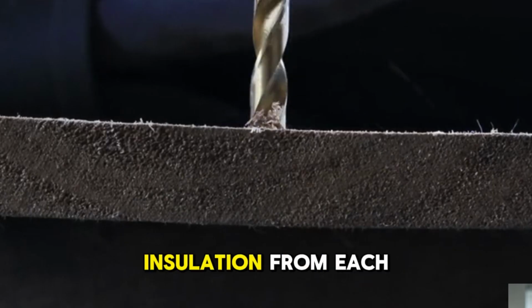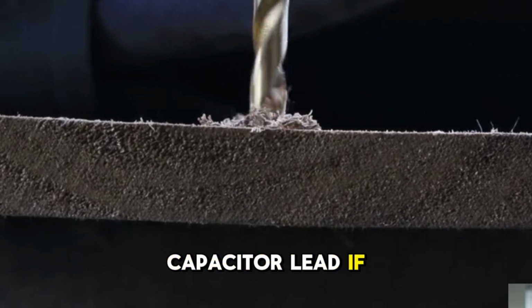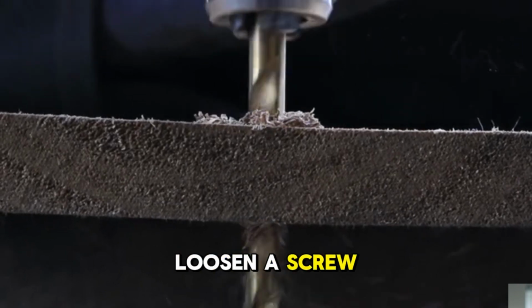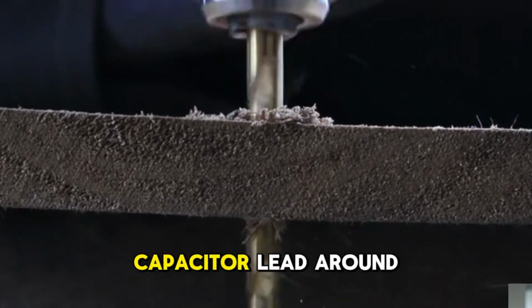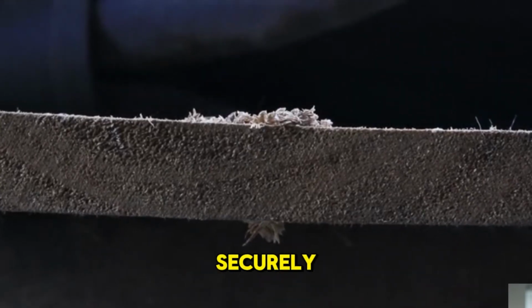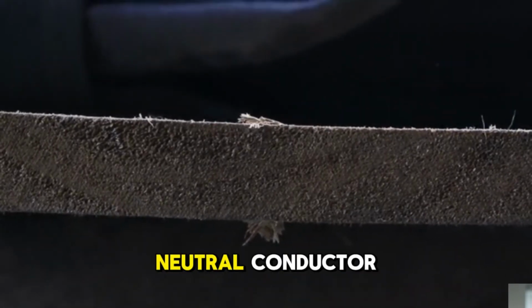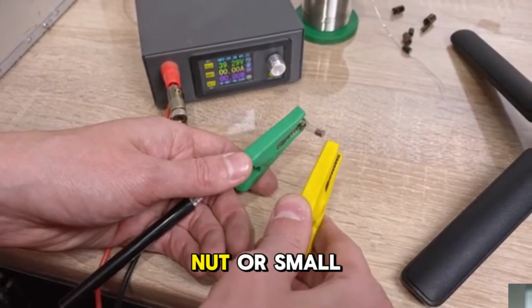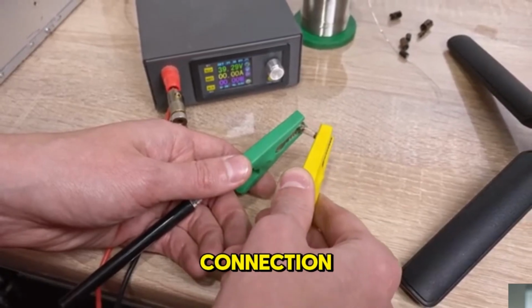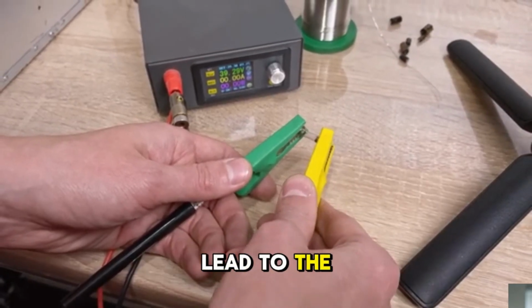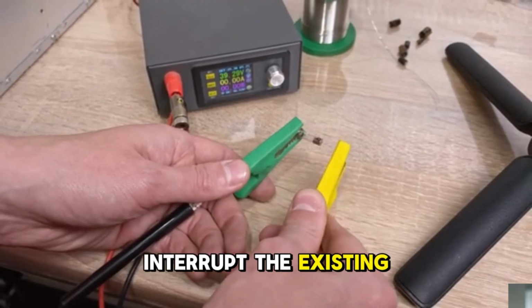Strip about 1/2 inch of insulation from each capacitor lead, if they're insulated. Loosen a screw on the ground bus bar and wrap one capacitor lead around the screw, then tighten it securely. The other lead connects to the main neutral conductor. You may need to use a wire nut or small crimp connector to make this connection, attaching the capacitor lead to the neutral line in a way that doesn't interrupt the existing connection.